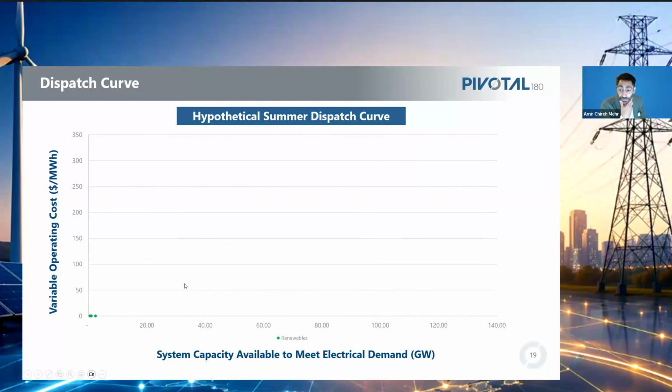So what's going to happen is first you're going to run the cheapest power plants, which happen to be typically your renewables, and by that I mean specifically wind and solar. While I'm exaggerating a little, they operate for free once you build them. The sun, until someone figures out to the contrary, still shines for free. The wind blows for free, and they oftentimes in their underlying agreements with the grid have what's called a must dispatch, must run agreement with the interconnection authority, the utility. So they get to sell everything they produce, and they go first, right?